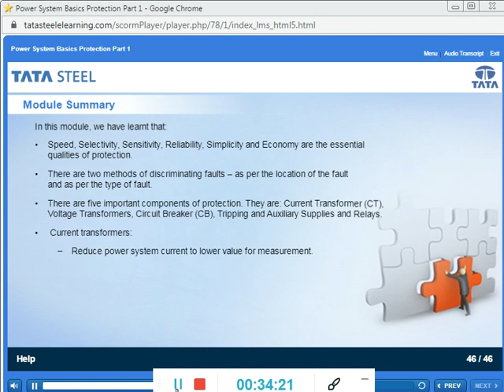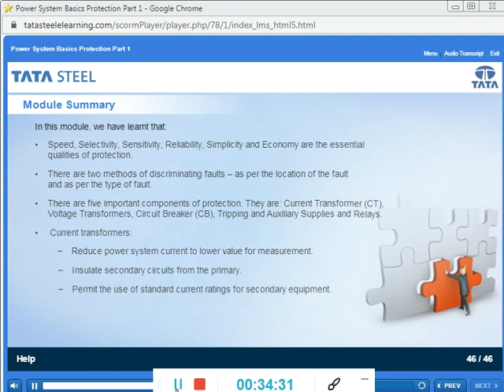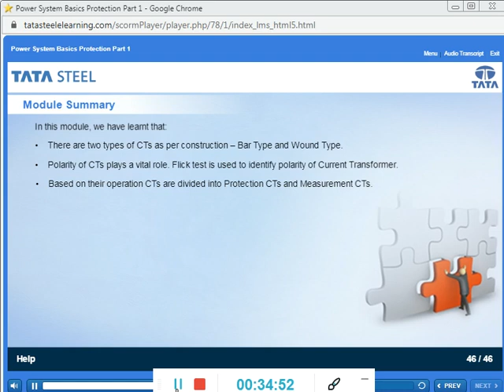Current transformers reduce power system current to lower value for measurement, insulate secondary circuits from the primary, and permit the use of standard current ratings for secondary equipment. There are two types of CTs as per construction, bar type and wound type. Polarity of CTs plays a vital role. Flick test is used to identify polarity of current transformers. Based on their operation, CTs are divided into protection CTs and measurement CTs. There are two basic types of VTs, electromechanical VTs and capacitor VTs. A circuit breaker is a switching device that interrupts the abnormal or fault current.